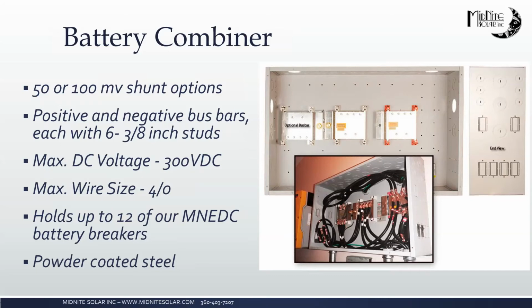It's rated for up to 300 volts DC. Max wire size per UL for bending room is 4/0. I have seen a lot bigger wire installed in this, but if the inspector does look at bending room, if you have to bend the wire, 4/0 is the largest. It has knockouts for up to 12 of our MNE DC breakers. You can use anywhere from our 5-amp breaker with our breaker adapter all the way up to our 250-amp breaker. So that's pretty handy if you're doing multiple strings of, say, lithium batteries or AGM batteries.